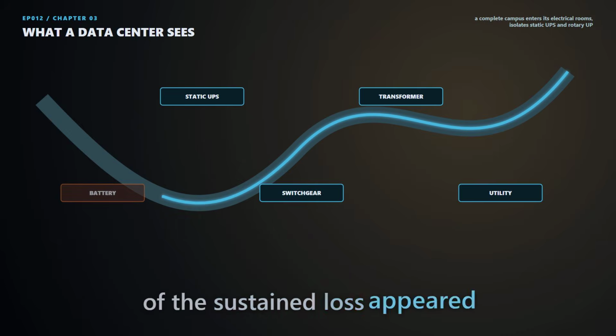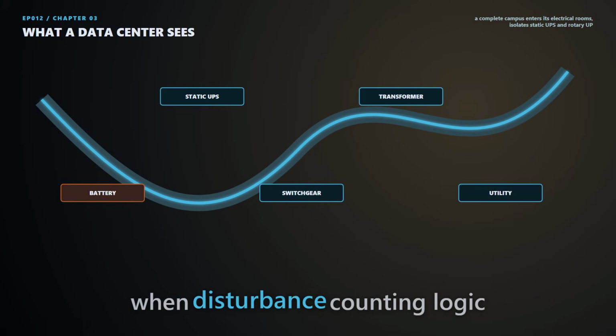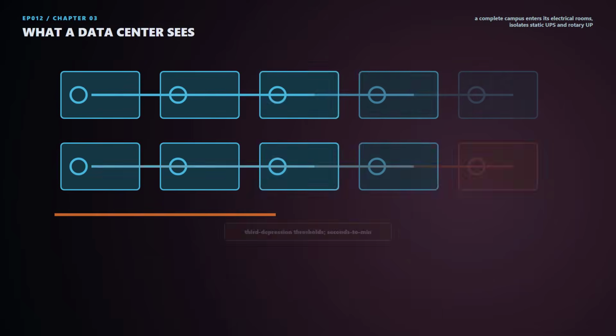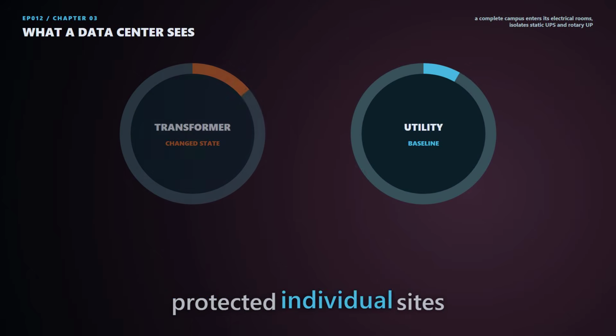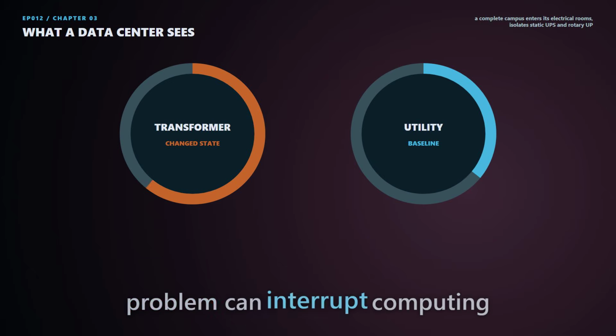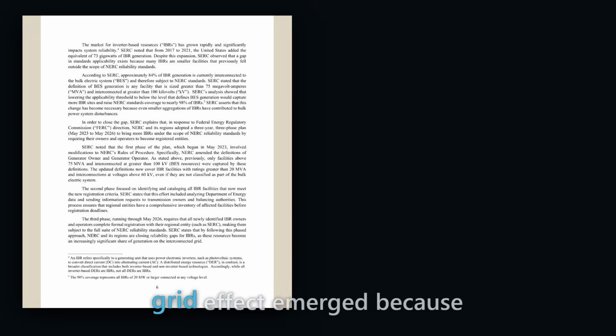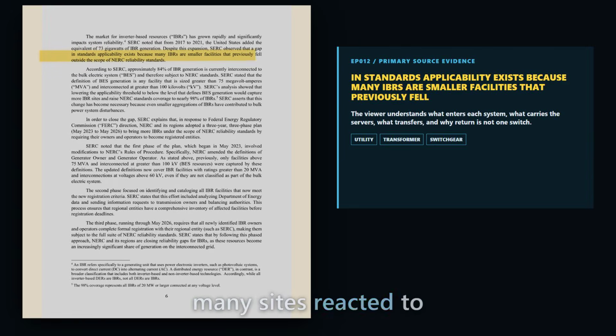Much of the sustained loss appeared after the third voltage depression, when disturbance counting logic at multiple sites reached its threshold. The settings protected individual sites where a small power quality problem can interrupt computing or corrupt work. The grid effect emerged because many sites reacted to the same sequence.